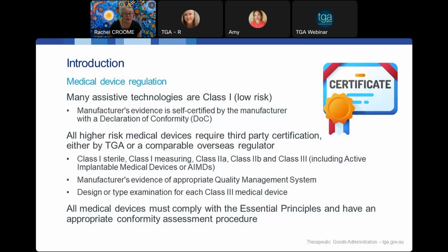So we're looking here at class 1. These processes are all self-certified by the manufacturer, who makes a declaration of conformity to affirm that this has been applied. Third-party certification of that is not required, but the manufacturer still needs to have evidence of compliance with the essential principles and that appropriate conformity assessment is in place, and provide this to TGA on request through the sponsor. And the sponsor must have a relationship with the manufacturer to be able to get this evidence as required. So it's quite difficult to comply with the regulatory requirements if you only have a contract of sale. You'll generally need a relationship with the manufacturer.